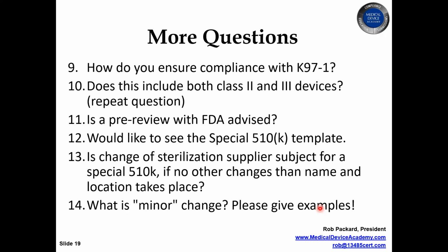But I think the earlier question where the person described their approach, they use their existing 510K template, which I make available to people that take my course. And then I modify that, use it sort of as a shell, and many of the sections become not applicable because there are no changes, or I say in that section, there are no changes from the previous submission. You use the same device as your predicate, so the earlier version of the device as your predicate, and basically all your changes are going to cover one functional area. And instead of presenting test reports, you're going to instead be submitting FDA Form 3654, the Declaration of Conformity, and you're going to summarize the changes that you made rather than providing the test reports.